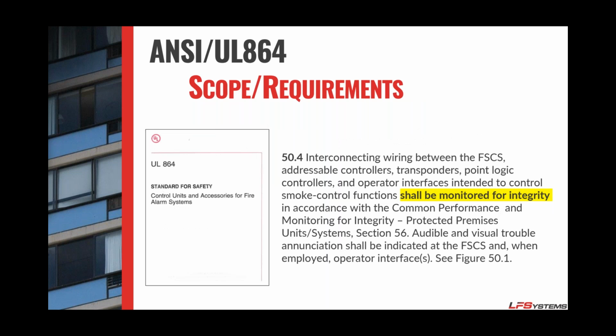And one of the main functions of UL and that listing is something called circuit integrity. So just for reference, most of my draft controls, my laundry exhaust controls, makeup air systems, they all have a simple start-stop contact. If you want that to run, you close that contact. If you want it to stop, you open the contact. It's a light switch. It's very simple. We all understand on, off.